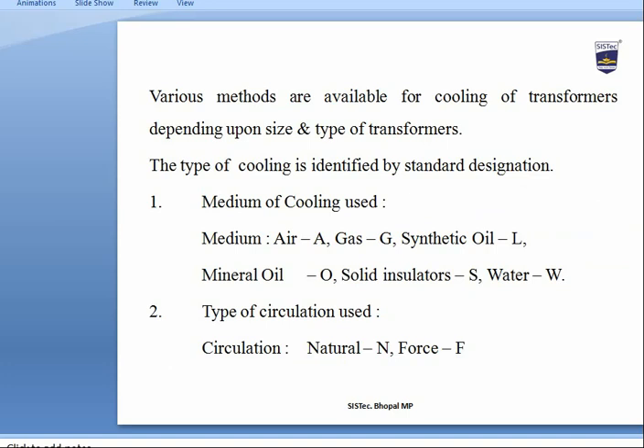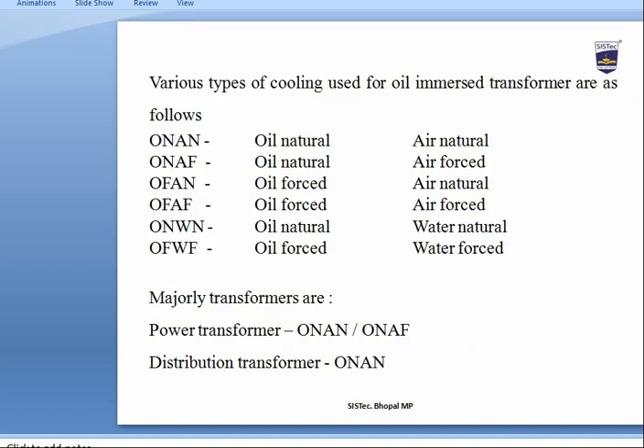Various cooling methods are available depending upon the size and type of transformer. The type of cooling is identified by standard designations: the first medium of cooling — Air (A), Gas (G), Synthetic oil (L), Mineral oil (O), Solid insulators (S), Water (W). Circulation types are Natural (N) and Forced (F).